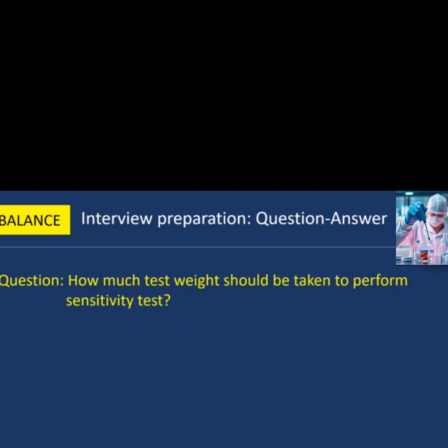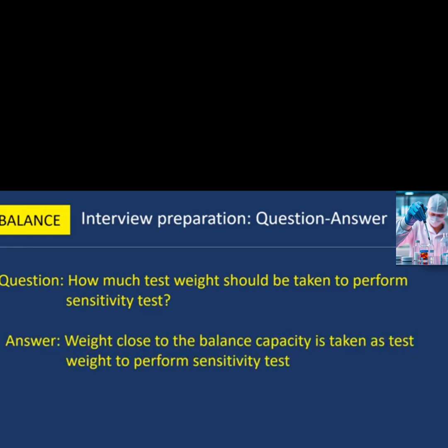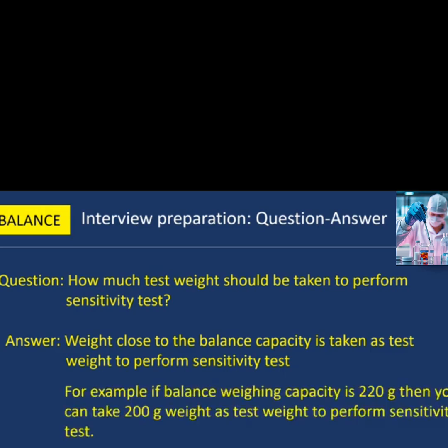Next question: how much test weight should be taken to perform the sensitivity test? A weight close to the balance capacity is taken as test weight to perform the sensitivity test. For example, if the balance weighing capacity is 220 grams, then you can take a 200 gram weight as the test weight.